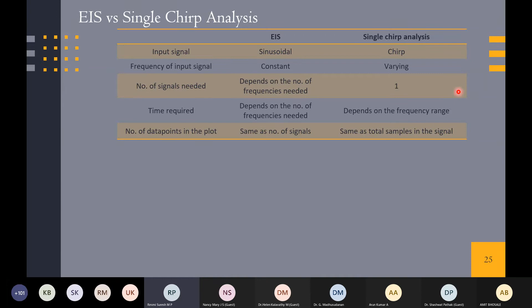The time required in EIS depends on the number of frequencies needed. Here in chirp analysis, it depends only on the frequency range. For example, if it is from 0.1 Hertz to 10,000 Hertz, you might be able to get the chirp response in 2 seconds. But when you go to a wider range in the lower frequency regime, say 10⁻³ to 10,000 Hertz, you can get the chirp response within 100 seconds.